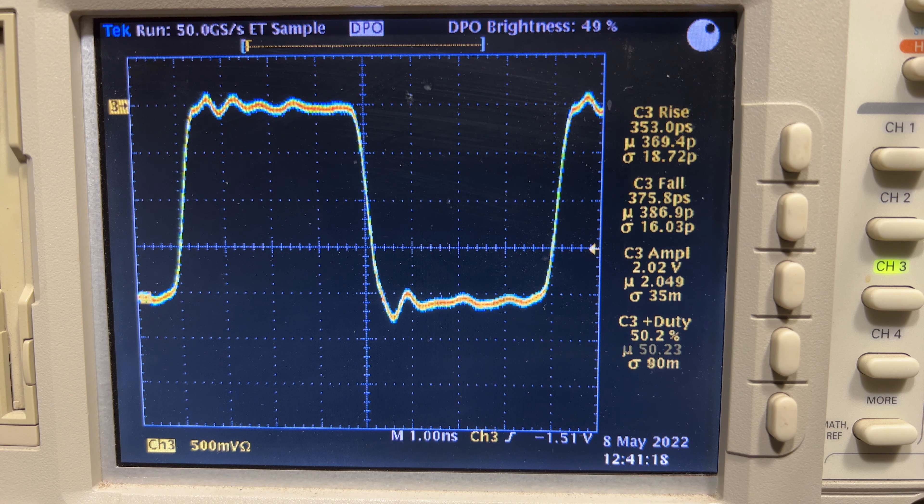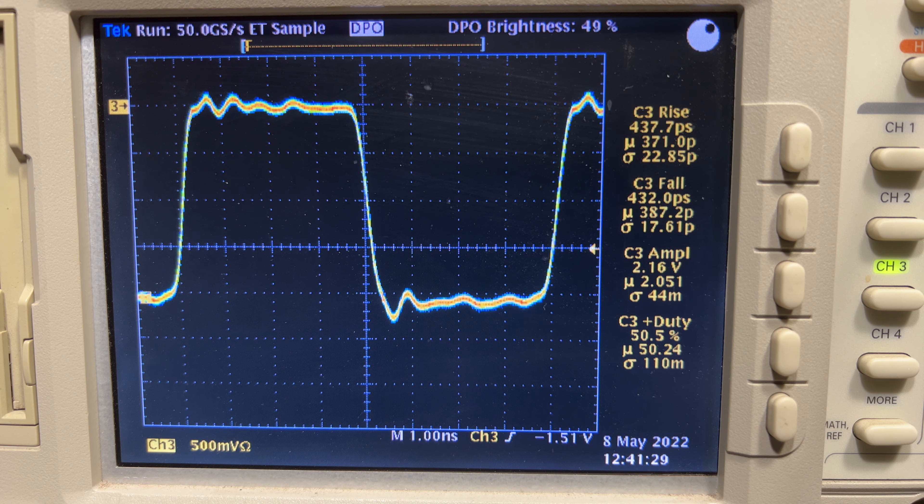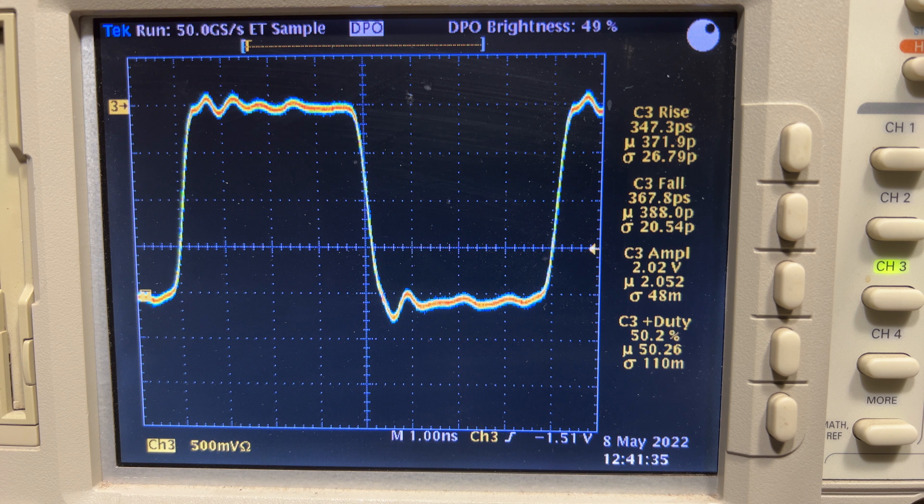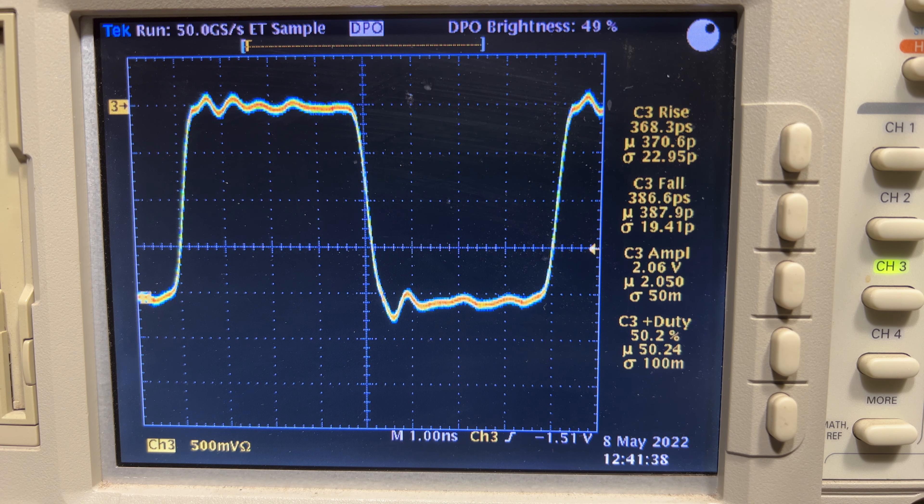Now we're zoomed in on the scope, making a measurement of the Colby Pulse Generator. We can see that the average rise time is running 360 to 370 picoseconds, and the average fall time is running between 380 and 390 picoseconds.